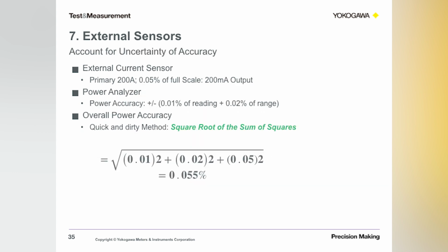Lastly, you also want to account for the stated uncertainty of that external sensor, right? If the accuracy is stated as 0.05% of full scale, then this accuracy needs to be added to the overall power accuracy. As an example, a quick and dirty way of doing this is basically the square root of the sum of squares, right? So in this example, if the power accuracy was stated as 0.01% of reading plus 0.02% of range, then you want to basically take the square root of the sum of squares. So you have 0.01 squared plus 0.02 squared plus 0.05 squared, which is of the external sensor, and take the root of that. So you will see that your uncertainty is 0.055.